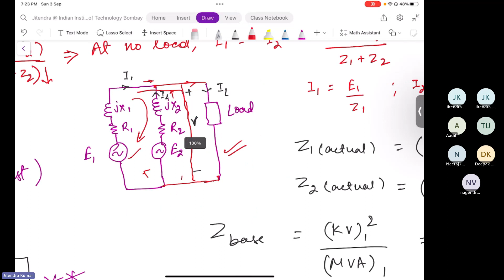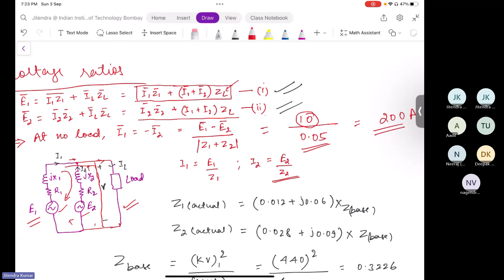So here, circulating current is E1 minus E2 divided by Z1 plus Z2, and E1 minus E2 is 10, and Z1 plus Z2, taking the mod, comes out to be 0.05. So it is 200 ampere. You see, very less leakage impedance, and very less difference in the no-load voltages. Also, the induced EMF difference is very small, 10 volts, and leakage impedance is very small, and because of this, your circulating current is very high, 200 ampere.